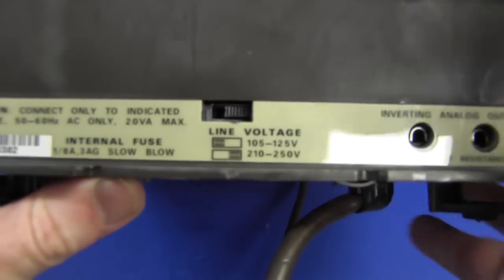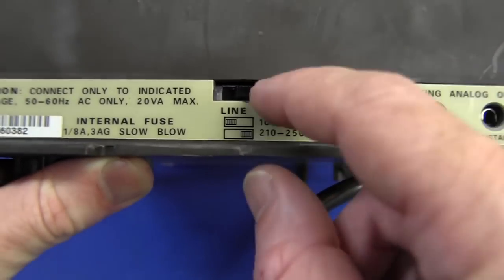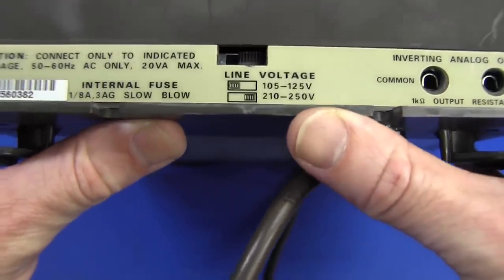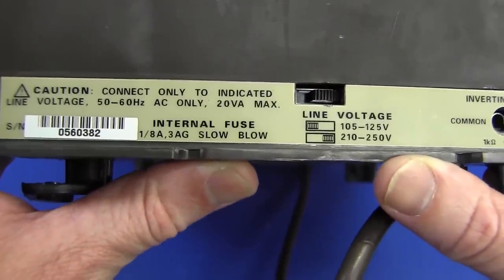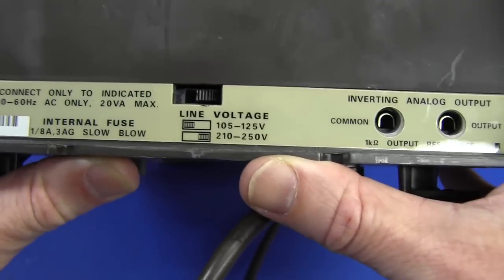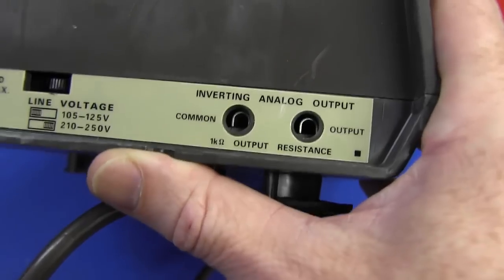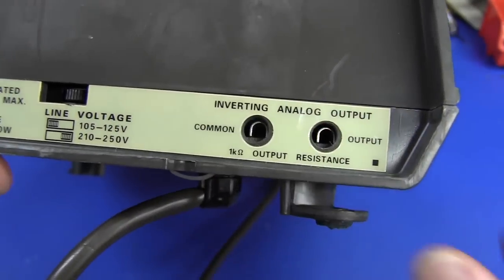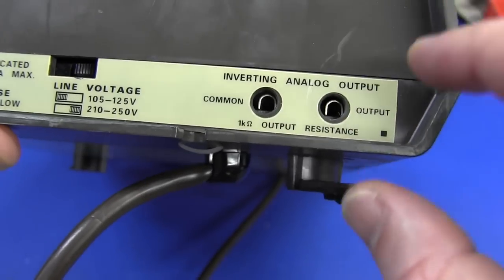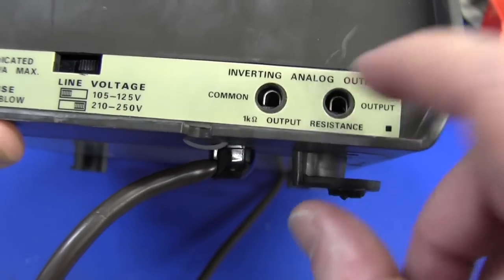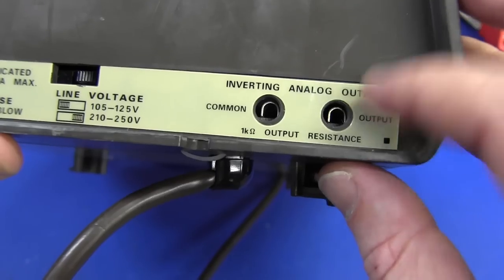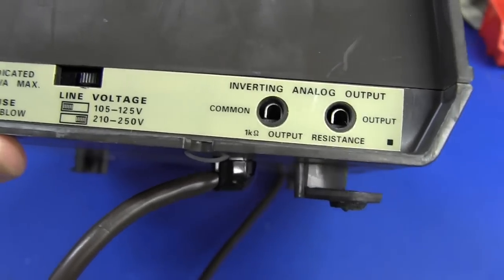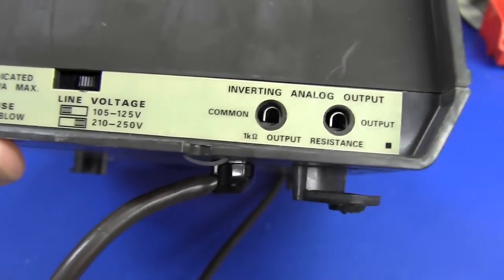Now, it's got a tilting bail here, and if we have a look on the back, it's got selectable 240 and 110. It's already set to 240 volts, so presumably that's not the reason why it is blowing. It's got an Australian plug on it, and we'll find out. It's got a couple of banana jacks on the output here, and the good thing about this is that it's the output directly from that feedback operational amplifier without going through any additional circuitry. So you can get the direct output from the feedback amp, which is really quite nice.